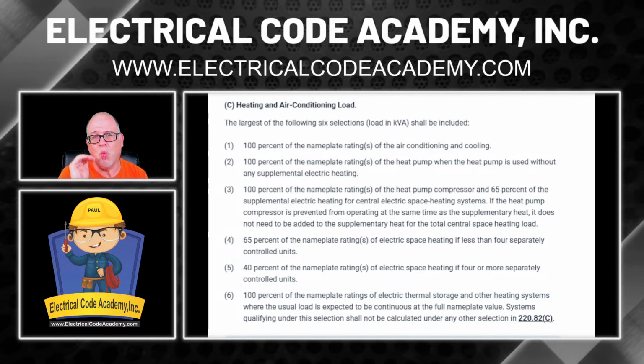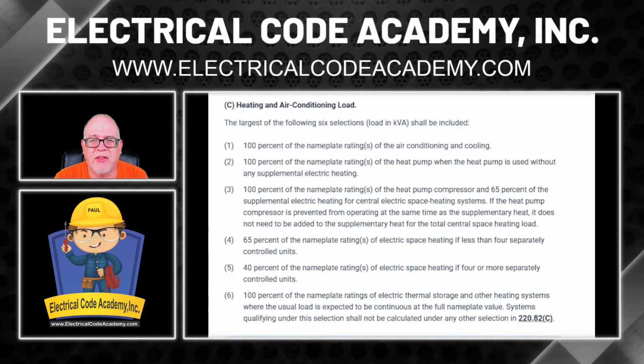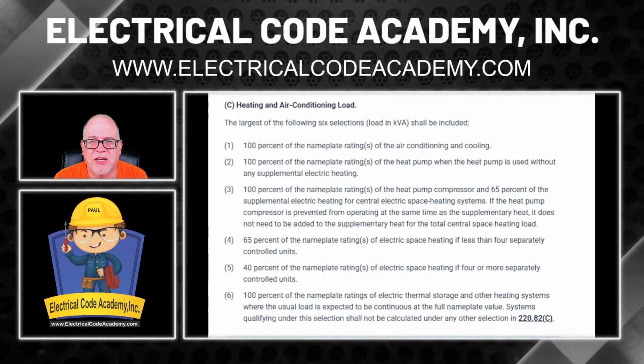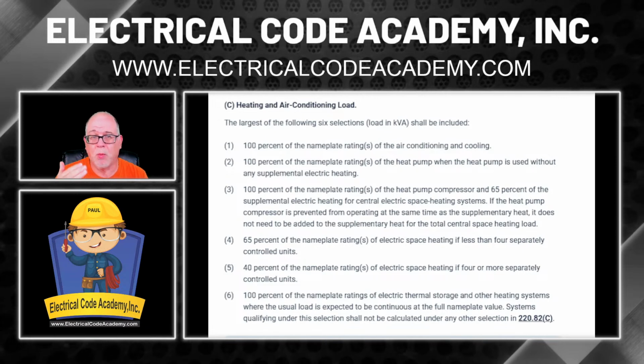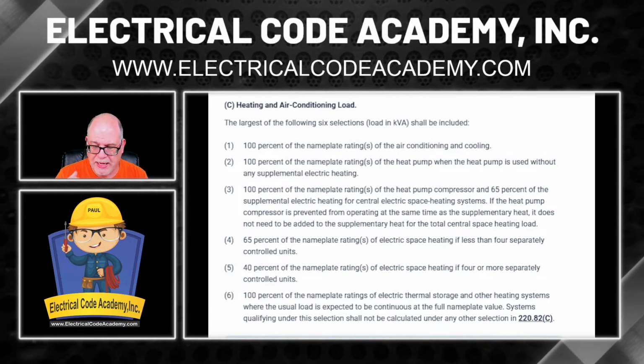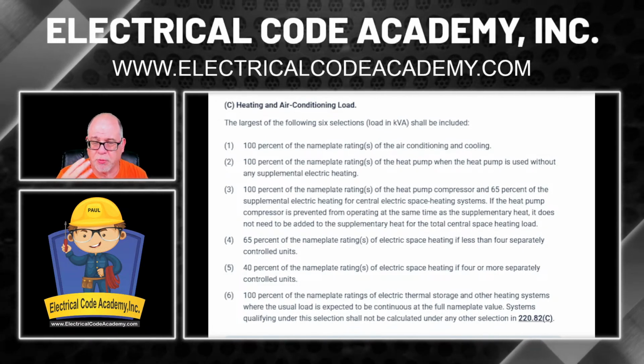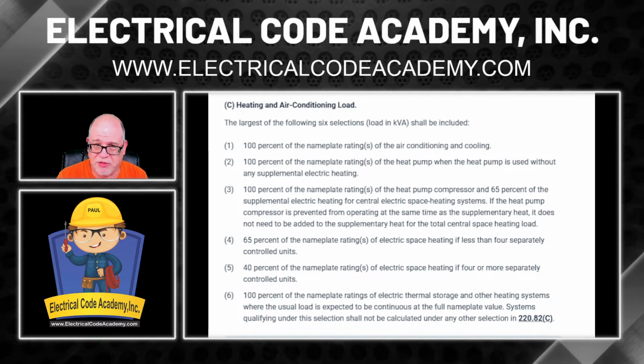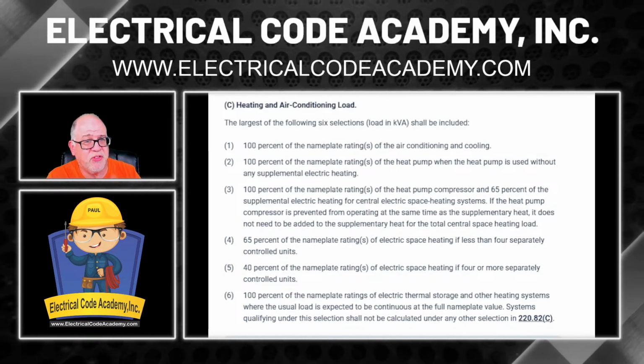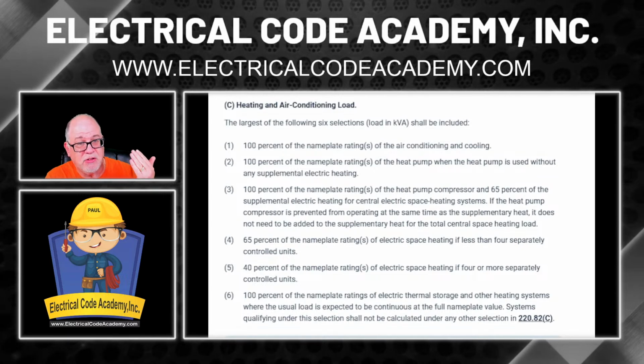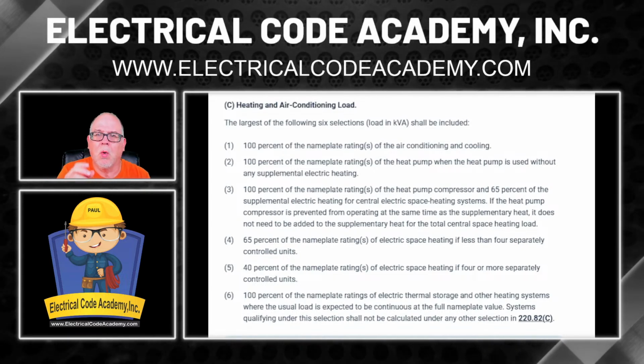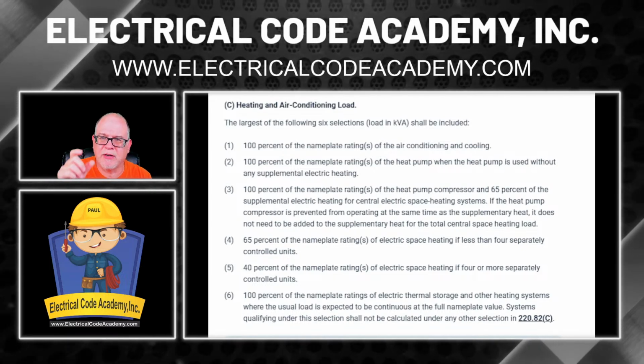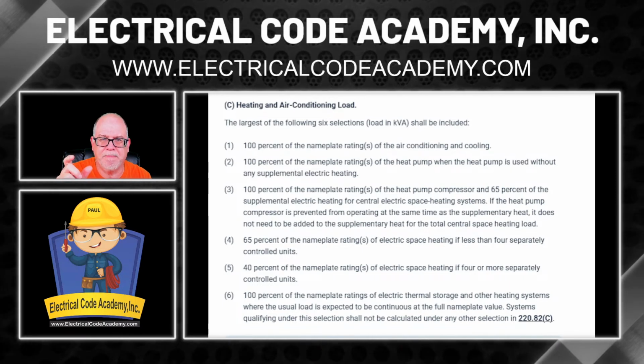Well, number 1 on this list says 100% of the nameplate ratings of air conditioning and cooling. Well, we already know what our air conditioning is. We had 2 of them at 10.5 amps and 3 of them at 7.2 amps. So we know what our air conditioning is. And we know our heat. There was 6 of them at 3 kW each. Okay, so we know that when it comes to the AC, we're going to take their full value at 100%.